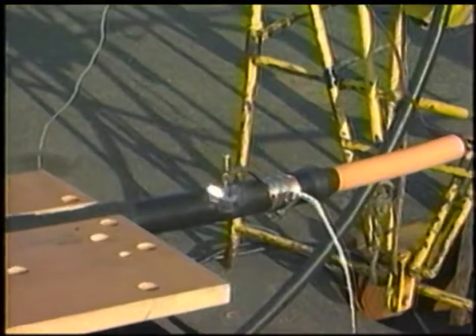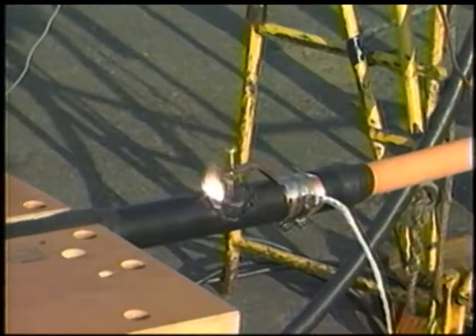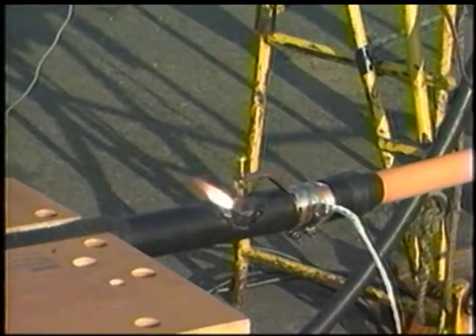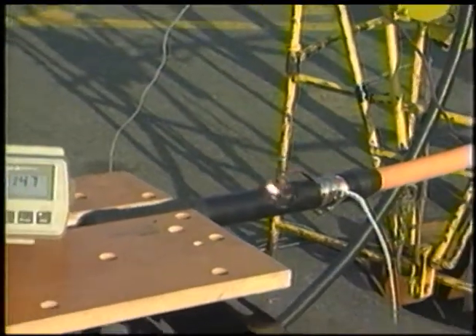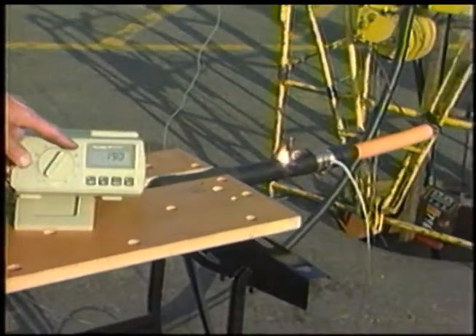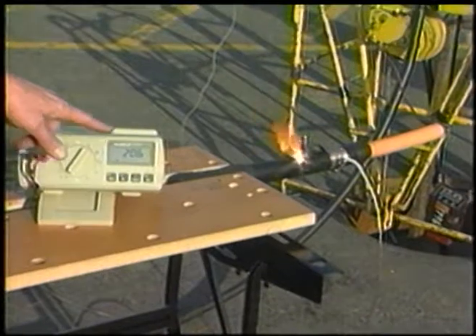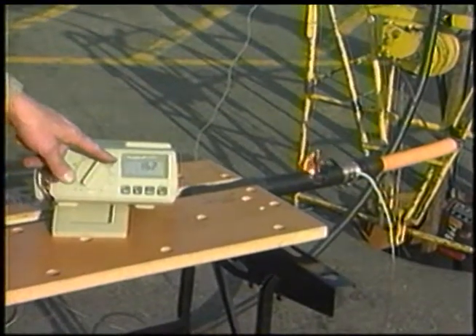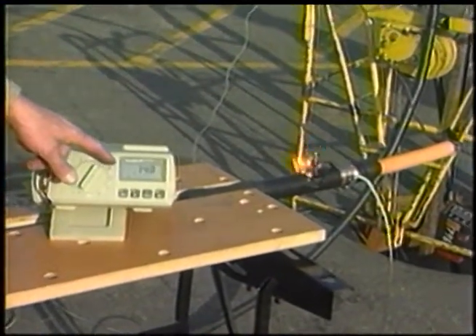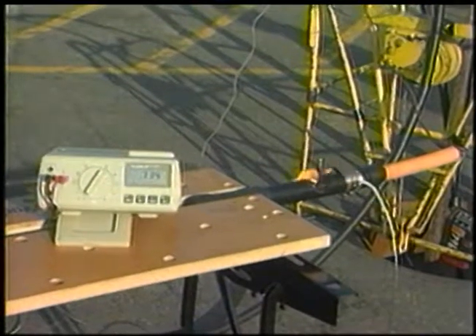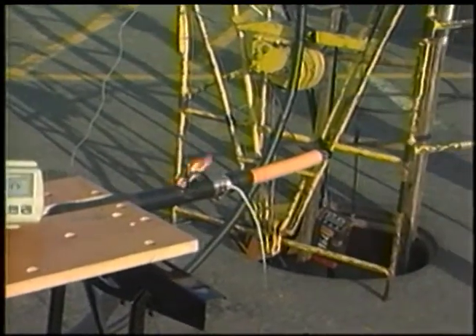Now the fault is jumping all over the place, as a fault will do, but the voltmeter, instead of reading 7.93 as you saw before, is only reading 0.2 in this case. That means we only have about 200 volts or 150 volts. Okay, Dennis, kill the generator.